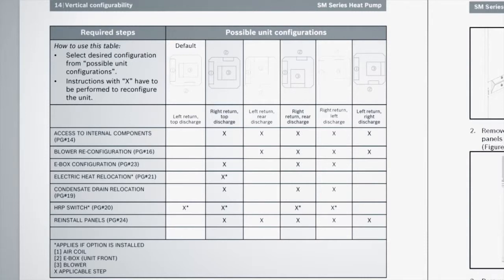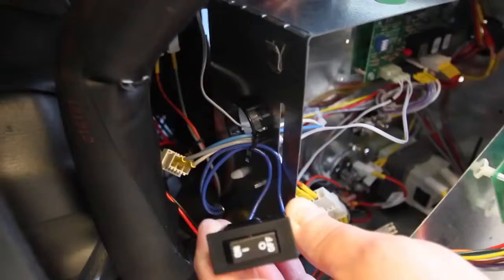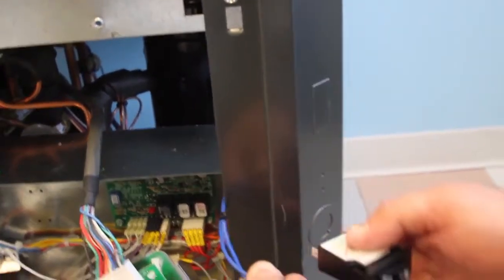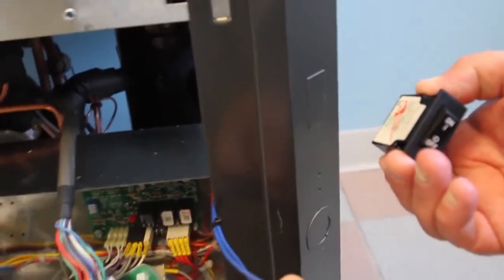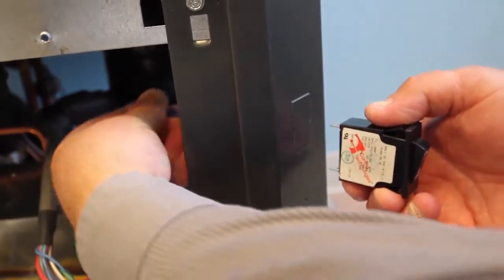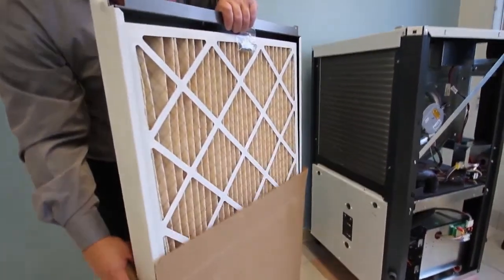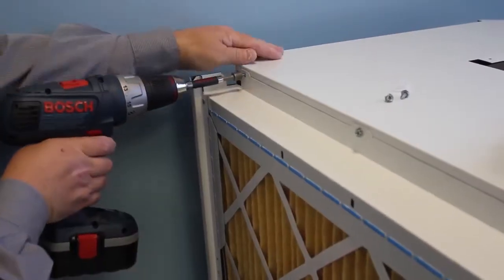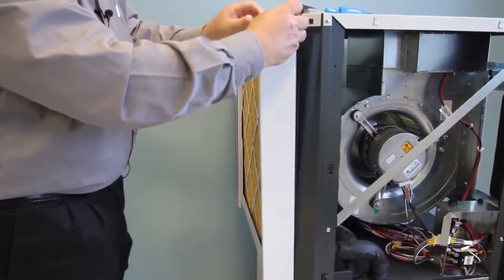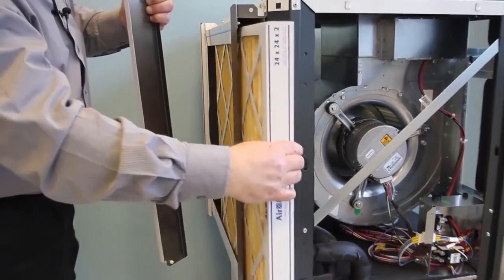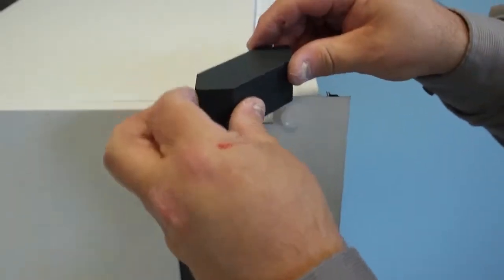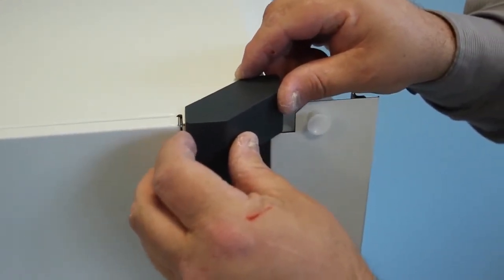There will be an X in the box where the desired configuration and each step intersect if that step is required. The default position, or as it is shipped from the factory, left-hand return air connection, top supply air connection, only requires you to do something if you have the hot water heat recovery package option installed at the factory. The HRP switch is shipped loose so that it can be installed on the front of the unit in the desired configuration. Once you have the HRP switch installed, you can attach the filter rack so that you have access to the front of the filter rack in the left-hand position. At that point, you are all set and ready to install the corner protectors and put the unit in place.